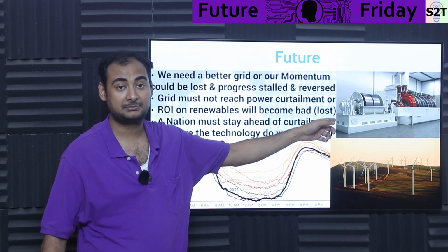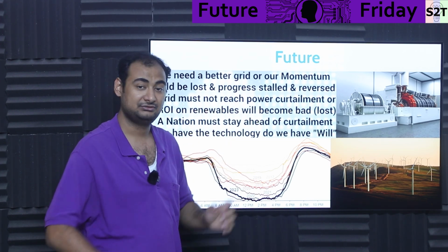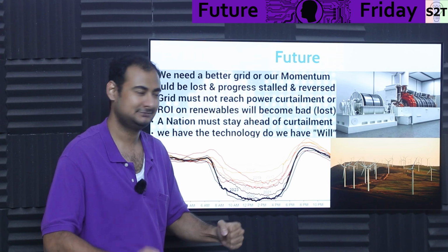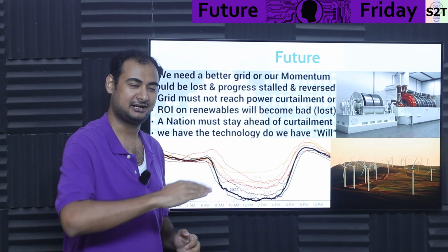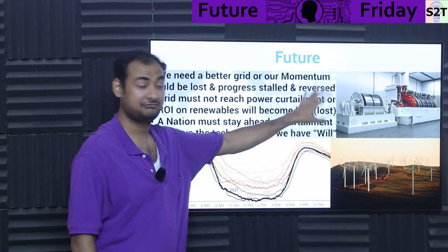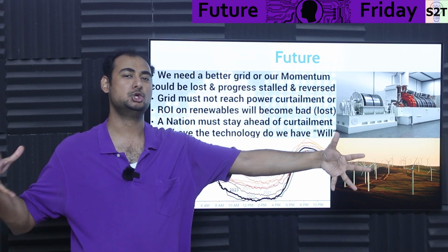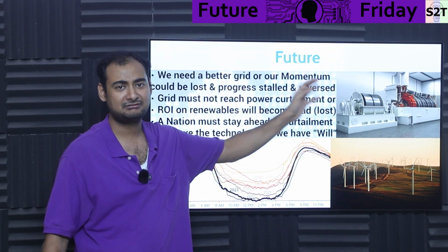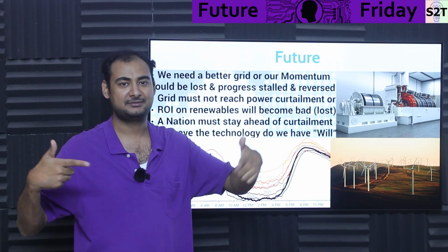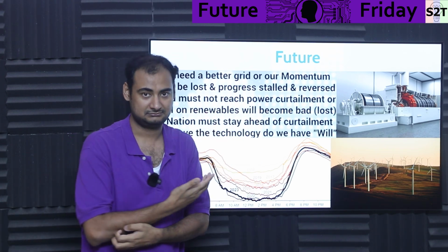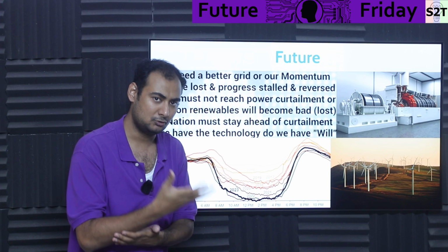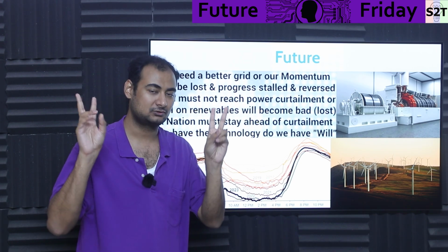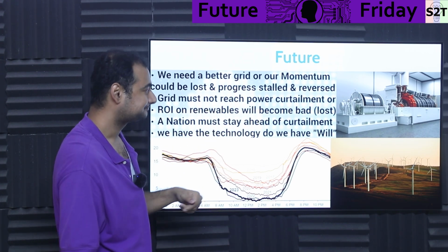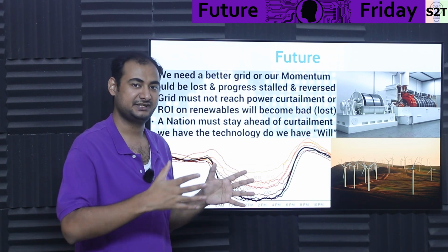And again, the ride-through capability of these things is awesome. So you have a surge, it can handle the surge and it's like, got this. They're very good. And you can even have a huge spinning mass. Wouldn't it consume power? A little bit. Once it is at the RPM, it does not change. It's not a load. It's basically a synchronous motor without a load. There is no, quote unquote, mechanical load on it. It's just a mass that is spinning, that is providing the inertia.